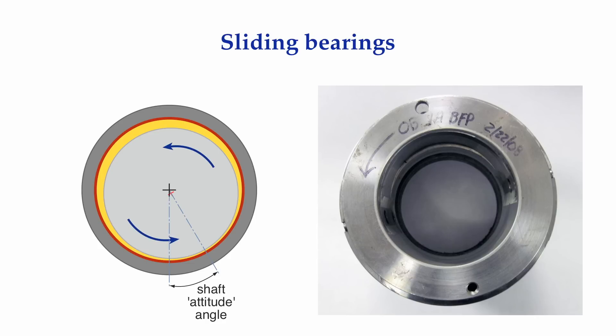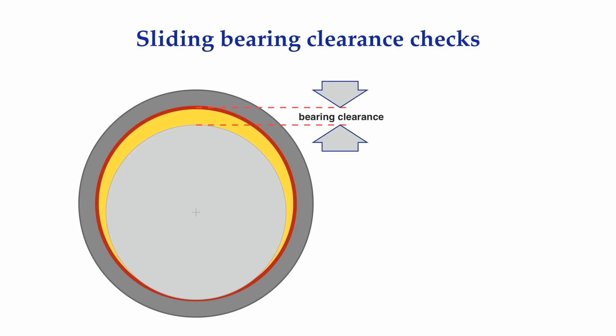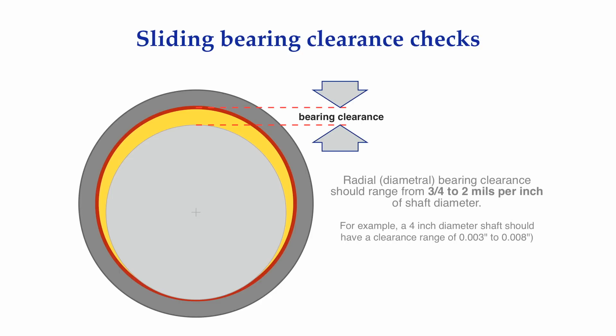Other common names for this type of bearing are journal bearings, plain bearings, babbitt bearings, sleeve bearings, bushings, and tilt pad bearings. These types of bearings require a certain amount of clearance between the shaft and the bore of the bearing, often referred to as the radial bearing clearance. This clearance typically ranges between three-quarters of a mil to two mils per inch of shaft diameter. One mil is equal to one one-thousandth of an inch. The term mil is also used as a unit of vibration measurement.